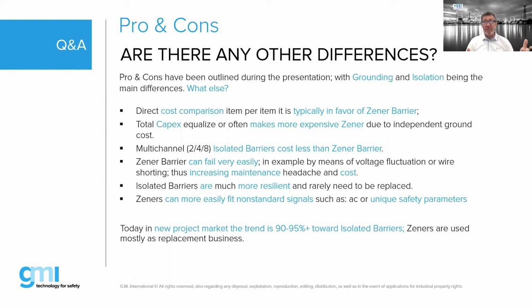If a failure happens, I mentioned thermocouple because it was a natural instance: in the thermocouple's jacket there is a thin wire, and there was vibration happening, and eventually the thermocouple itself grounded into the jacket, and the jacket is normally grounded. So you end up with a grounded thermocouple, which creates another problem called cold junction compensation. You're misreading it, but it also introduces quite a dangerous situation for Zeners.